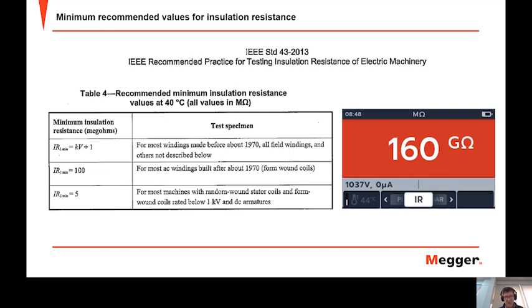And the important point to remember is that we must measure the winding temperature and then use that to correct to 40 degrees C. We can then trend those values over time, but we can also make sure that at 40 degrees C, we do have a value that's higher than the safe recommended minimum.